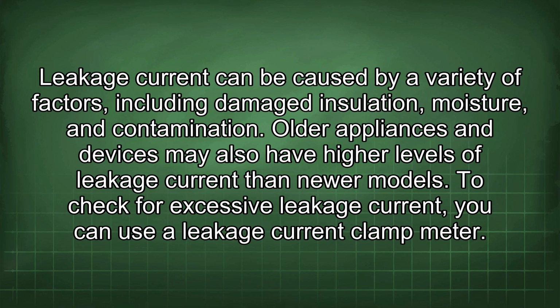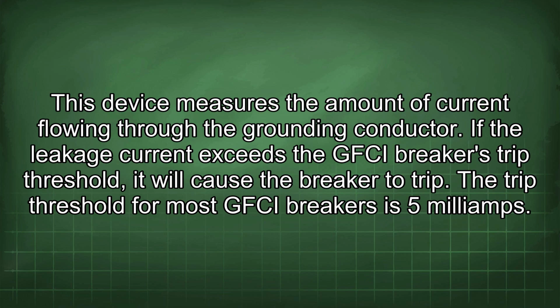To check for excessive leakage current, you can use a leakage current clamp meter. This device measures the amount of current flowing through the grounding conductor. If the leakage current exceeds the GFCI breaker's trip threshold, it will cause the breaker to trip. The trip threshold for most GFCI breakers is 5 mA.